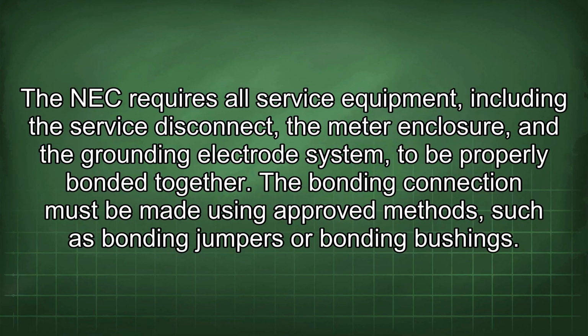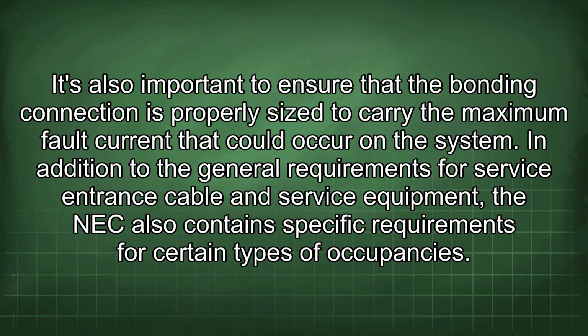The NEC requires all service equipment, including the service disconnect, the meter enclosure, and the grounding electrode system, to be properly bonded together. The bonding connection must be made using approved methods such as bonding jumpers or bonding bushings.